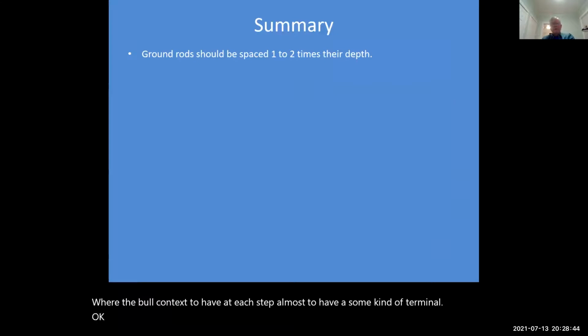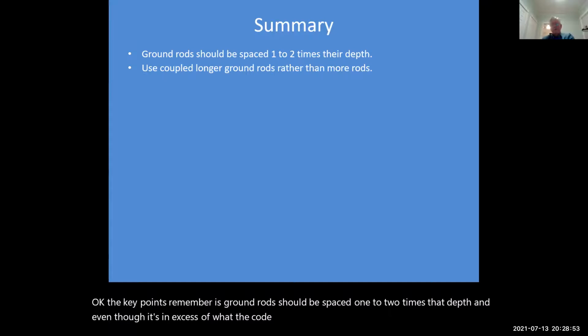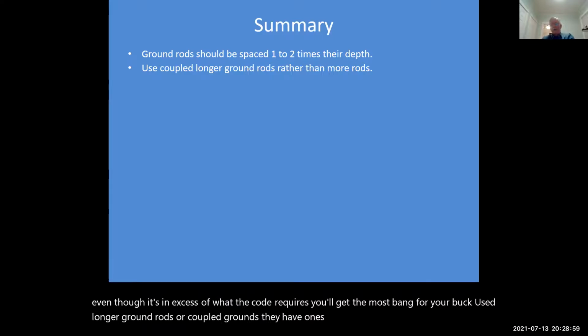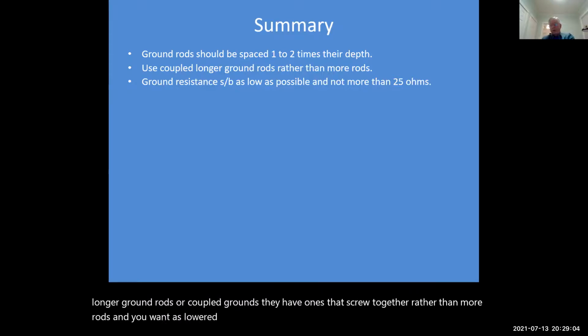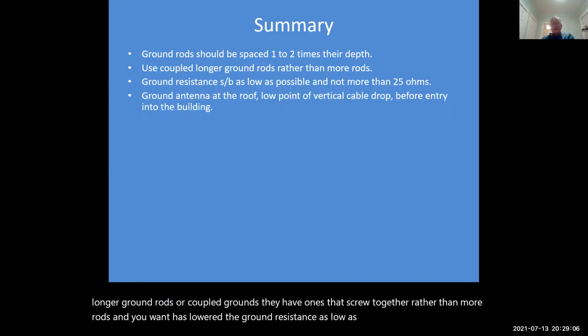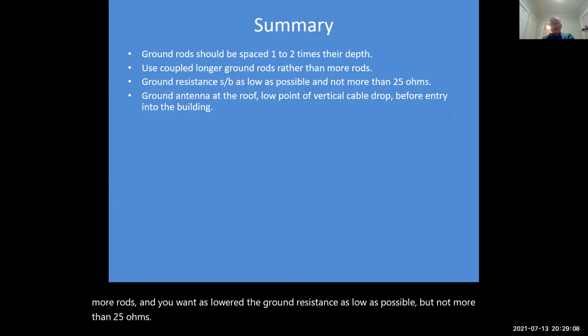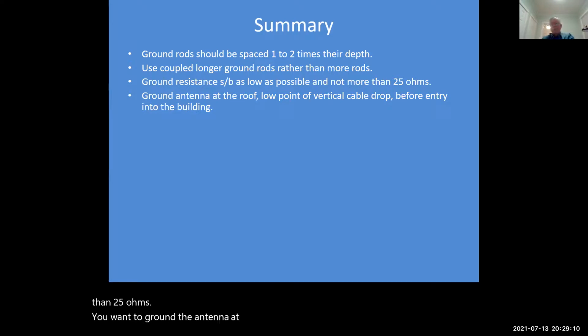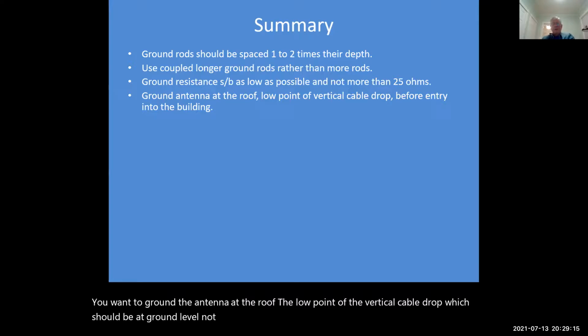The key points, remember, is ground rods should be spaced 1 to 2 times their depth. And even though it's well in excess of what the code requires, you'll get the most bang for your buck. Use longer ground rods or coupled ground rods. They have ones that screw together rather than using more rods. And you want to lower the ground resistance as low as possible, but not more than 25 ohms. You want to ground the antenna at the roof, the low point of the vertical cable drop, which should be at ground level, not midway, and before entering into the building.